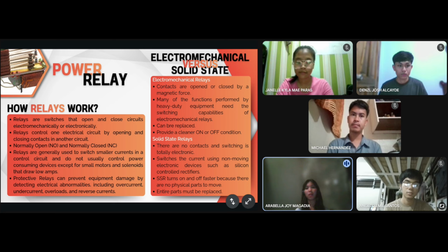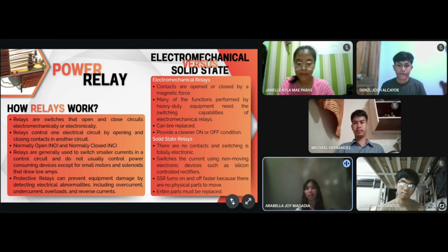Now let's move on to the two main types of relays, electromechanical and solid state. For electromechanical relays, they work with physical movement. Inside, there's a magnetic coil that pulls contacts together or apart. That's how the circuit opens or closes. Because of this mechanical motion, they can handle heavy-duty tasks like those in electrical machines. They also give a clear on and off state, and the best part is you can replace them if they wear out.